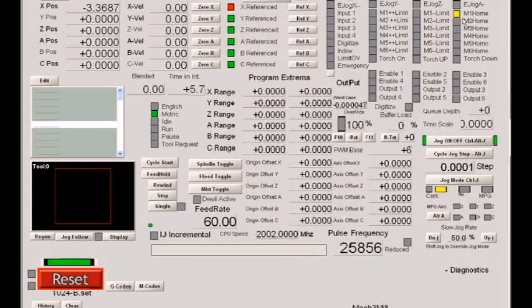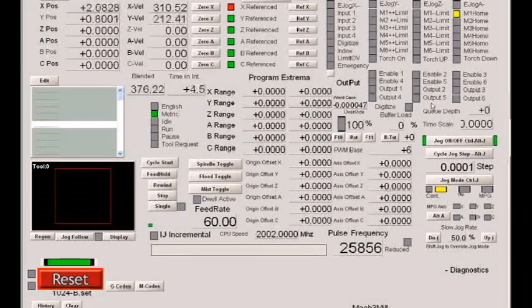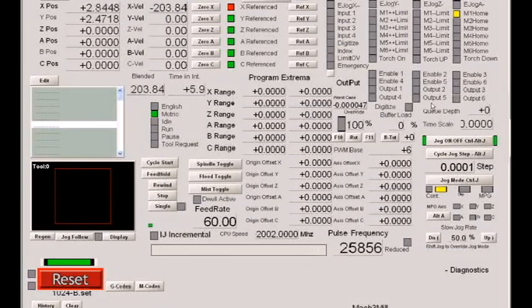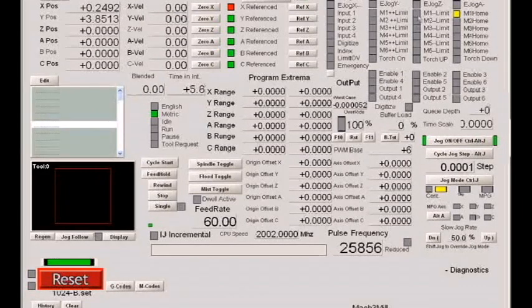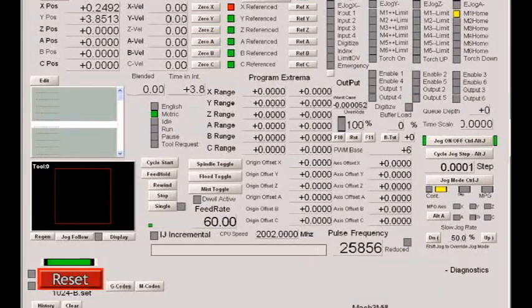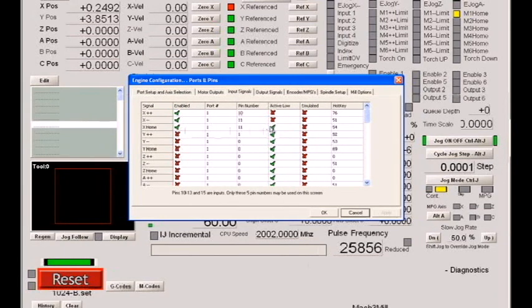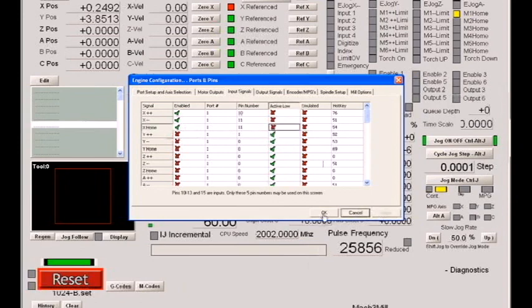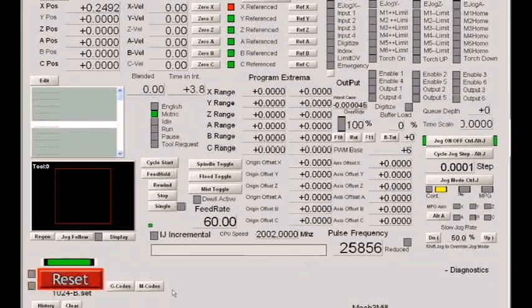You'll notice now, though, that when I reset, my home switch is lit. You won't see any effect to this error until you try to home. It's very important that you make sure that LEDs are out when the signal is not active. So we go to ports and pins, input signals, and you'll notice why we have that light lit. This active low is checked only for the home switch. So we'll uncheck that. And now the light goes out.